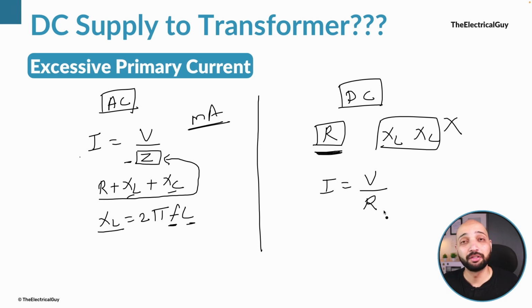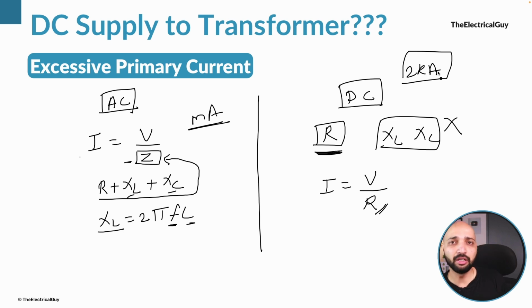And definitely minimum resistance means a high current, because there is no other opposition offered to the current than this minimum resistance. And that is the reason why you saw the current went up to 2 kiloampere when we connected the DC supply. And that is huge current. The transformer primary winding is not meant to carry this high current. Clear? So if this current is gonna flow continuously through the transformer, there will be overheating of the coil, overheating of the winding, and that is gonna burn that winding out.